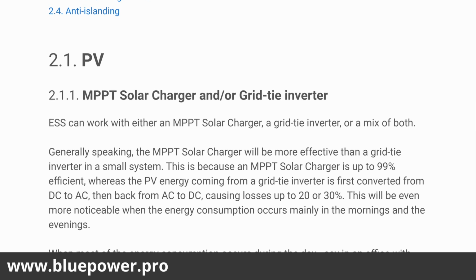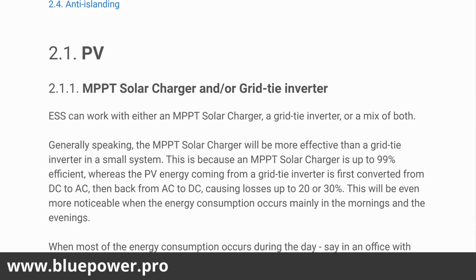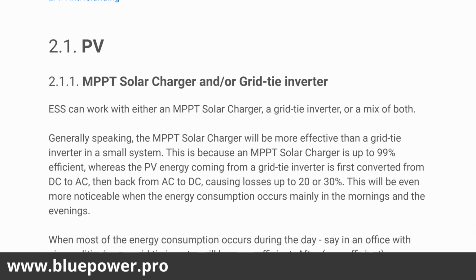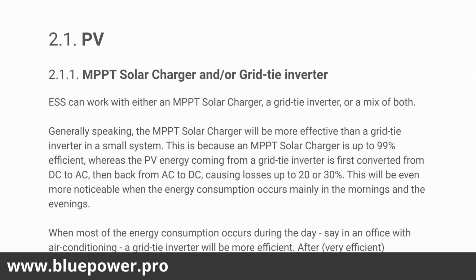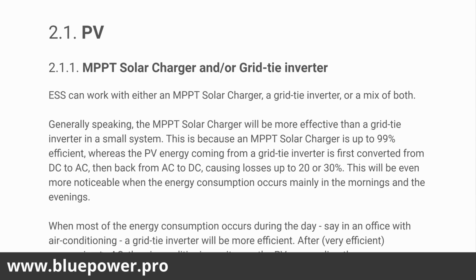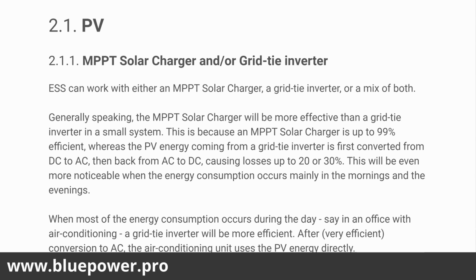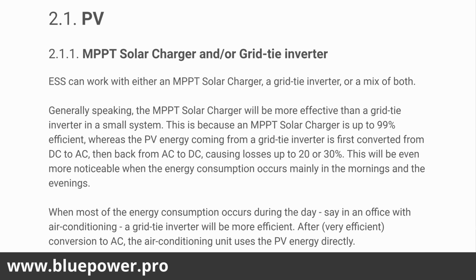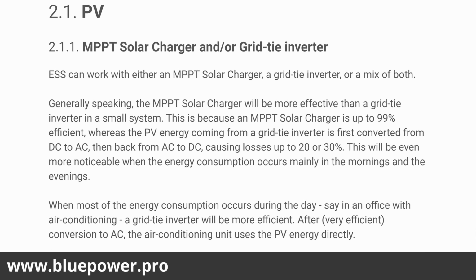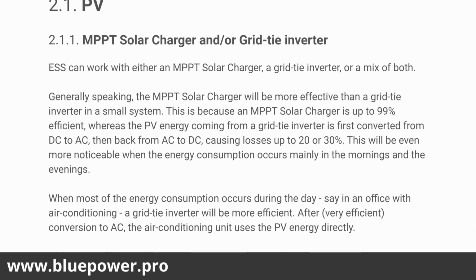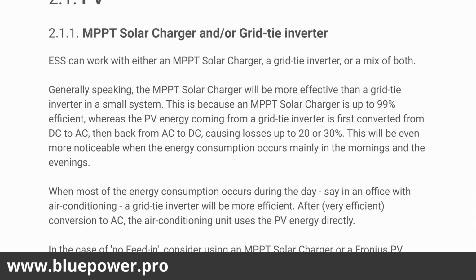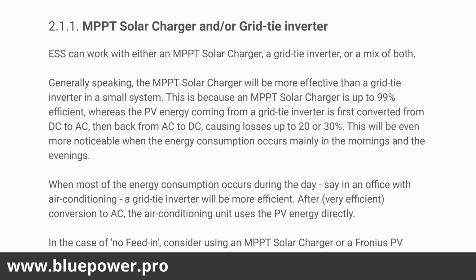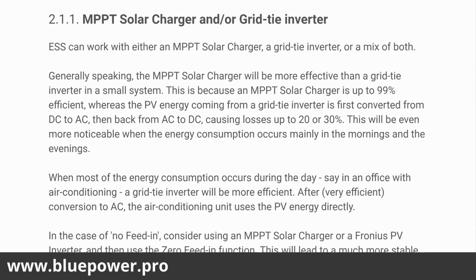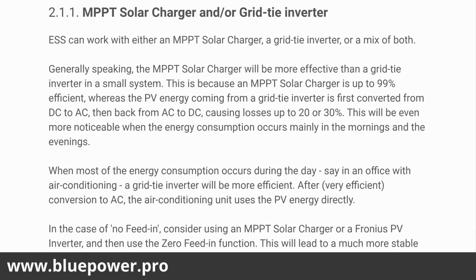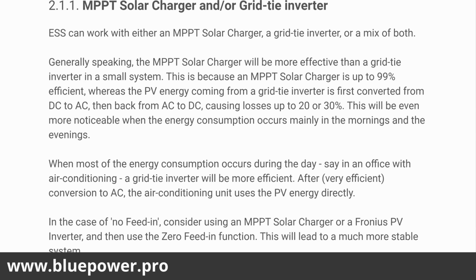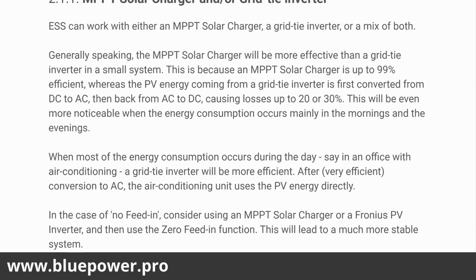So this will be even more noticeable when the energy consumption occurs mainly in the mornings and in the evenings. So when most of the energy consumption occurs during the day, say in an office with air conditioning, a grid-tied inverter will be more efficient. After very efficient conversion to AC, the air conditioning unit uses the PV energy directly. So that's if it's connected on the AC output, then it's only the conversion loss of your PV inverter that's taken into account. But if you're going to be charging your battery and running your loads at night, it's going to be more efficient to charge it with a DC MPPT.